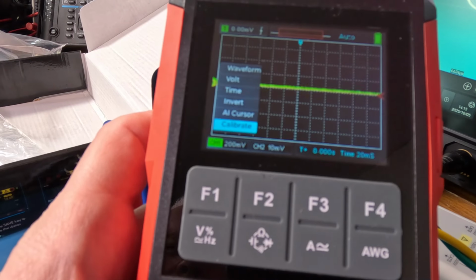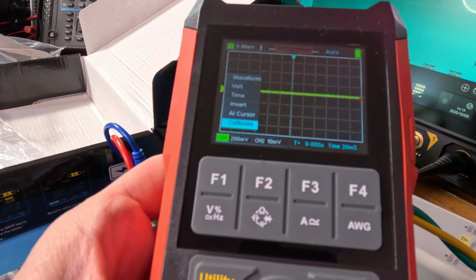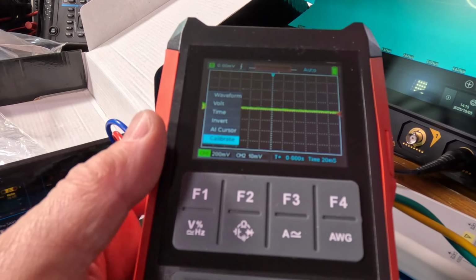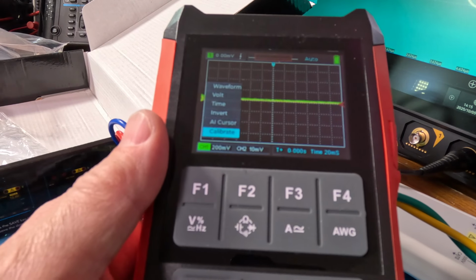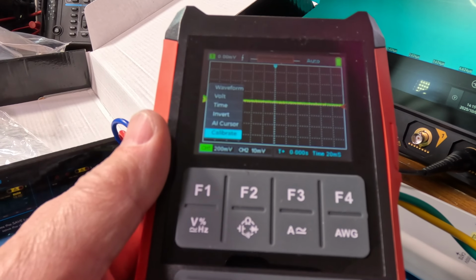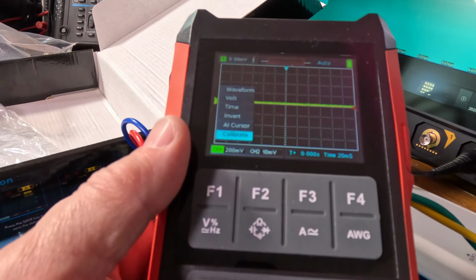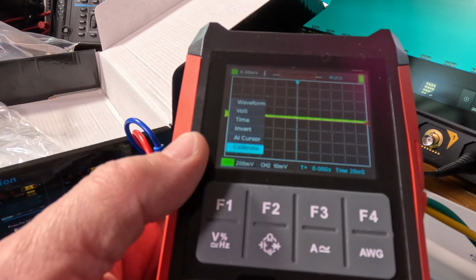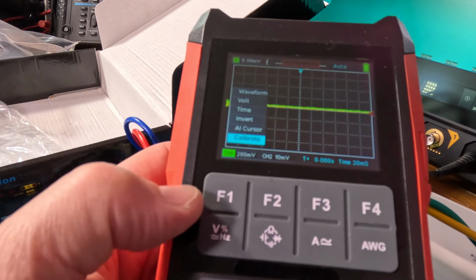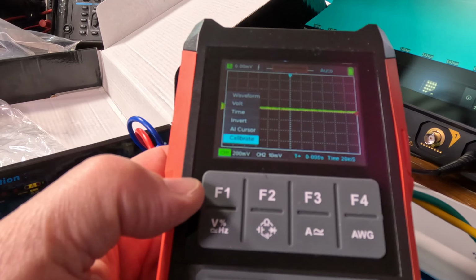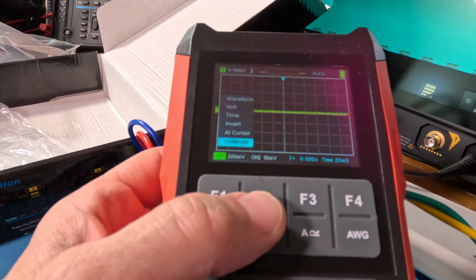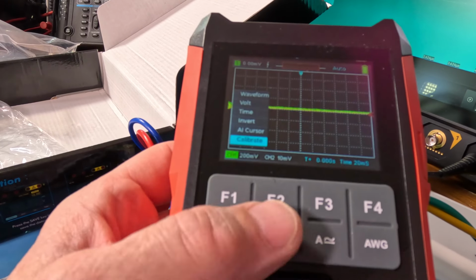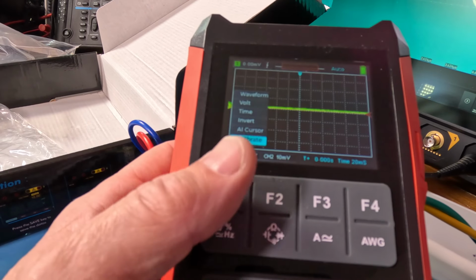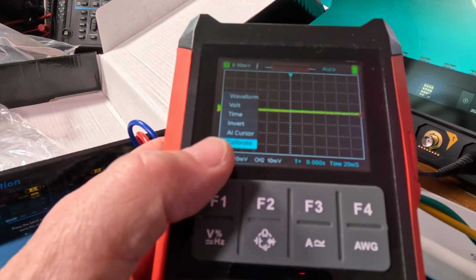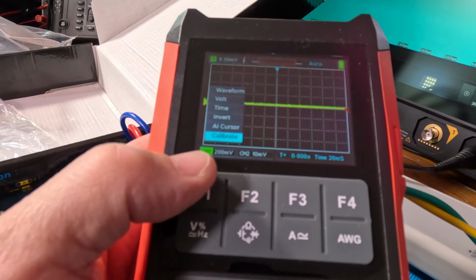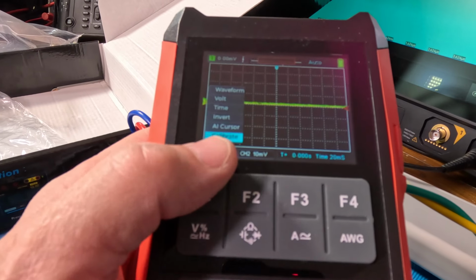Okay, and then there's calibrate mode, so we won't do that. But I recommend when you get a new meter, let it come to room temperature in the lab. Let it be on for probably 15 minutes and then calibrate it. If it's been in your lab for a while, it's probably at room temperature. When you turn it on, it's not going to draw a lot of power, so it's not going to heat up a lot and you don't have to wait too long. But I'd give it a little time. Just make sure the temperatures are all stabilized before you calibrate.